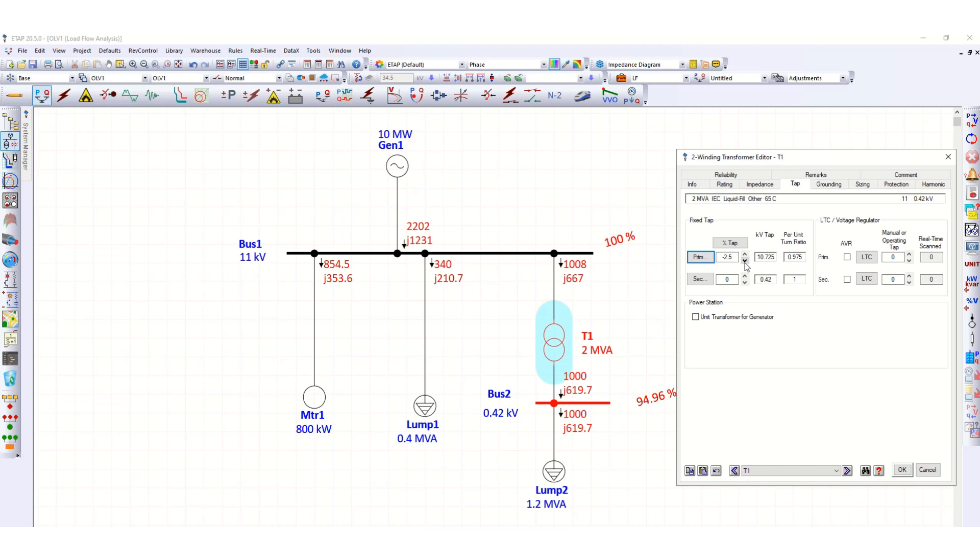Then kV primary side kV tap, here you can see this is changing. So at 0 this was 11 kV, at minus 2.5 percent this is 10.725 kV, at minus 5 percent this is 10.45 kV. So let's use this minus 2.5 percent tap over here.